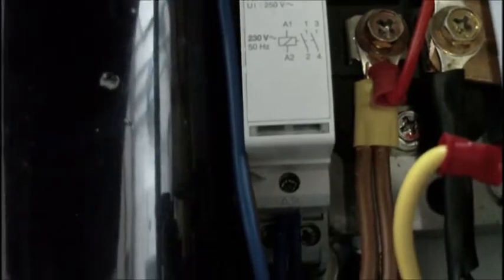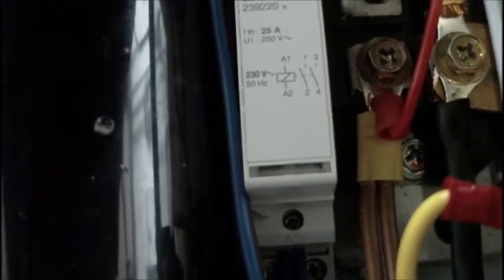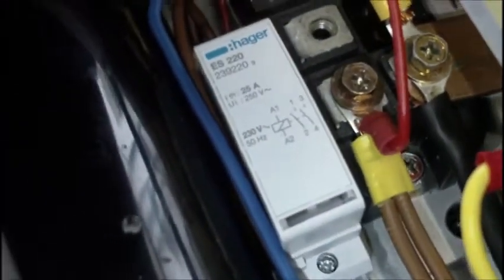And that comes over here to the rectifier. And I managed to squeeze in beside that a 25 amp two pole contactor, a small type. And this one has a 230 volt AC coil. And I was able to wire the contacts in parallel. So that should give me all of the current handling capability that I need.